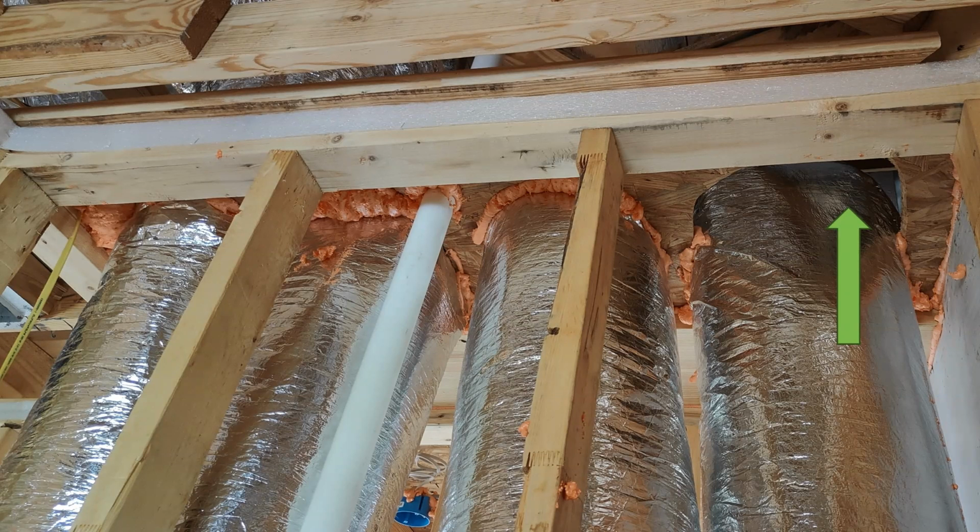And then the top is now required to be blocked and sealed. The blocking here has been done, but there is some air sealing that's lacking on the far right-hand side where that arrow is. Not sure what happened. Either they ran out of poly seal, or they just didn't get around to it, or for some reason it had to be cut bigger so the duct would have less crushing around it. Not really sure what happened. But it should all be sealed here.